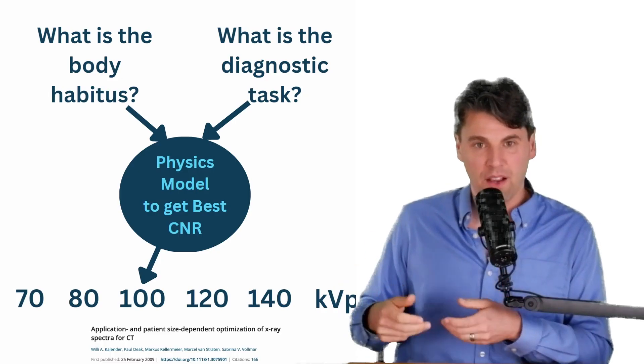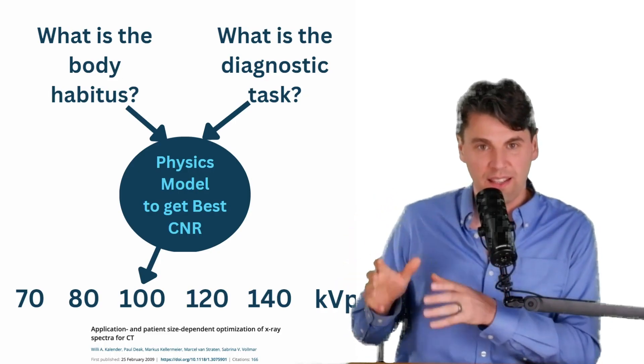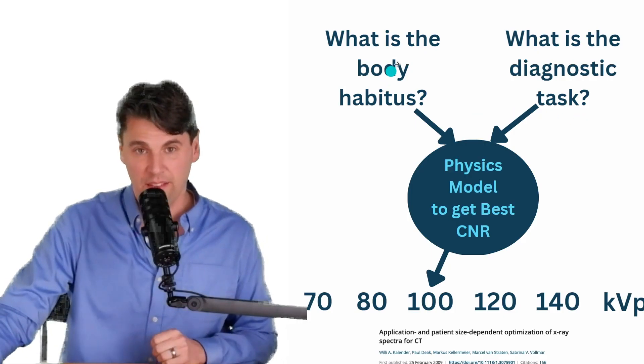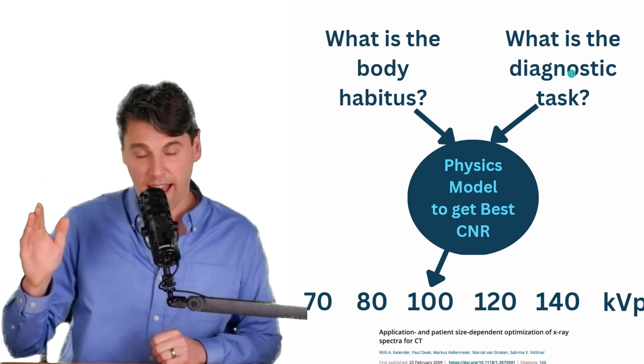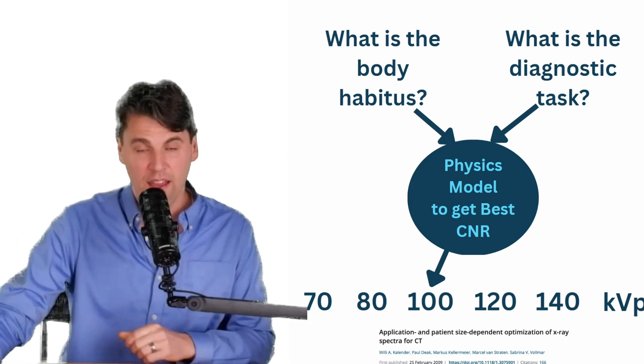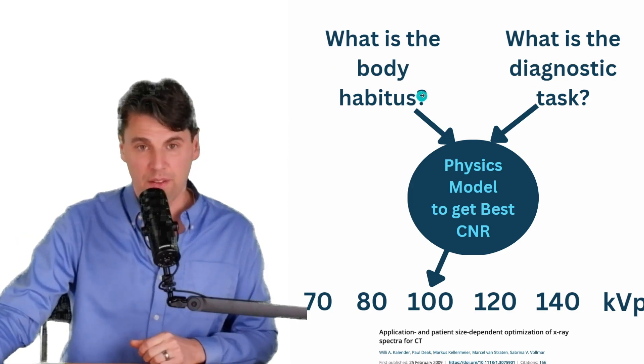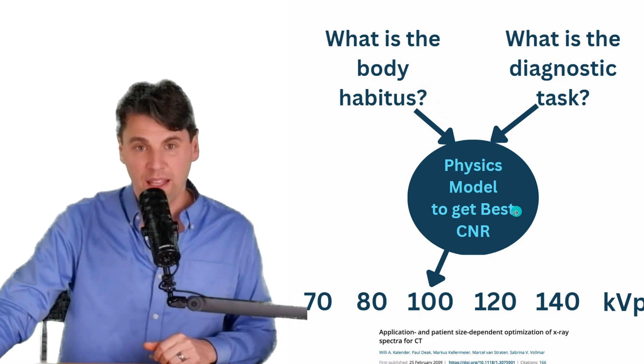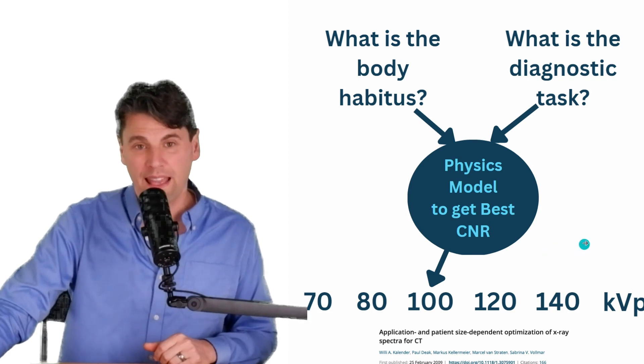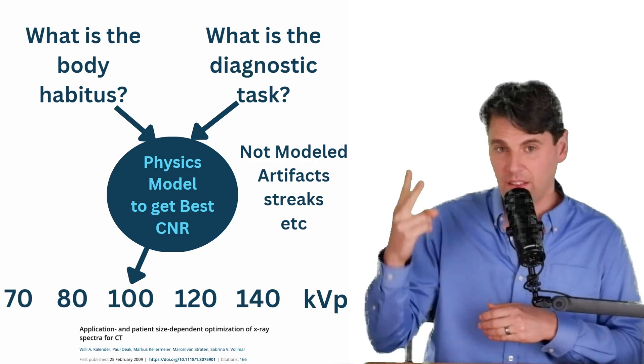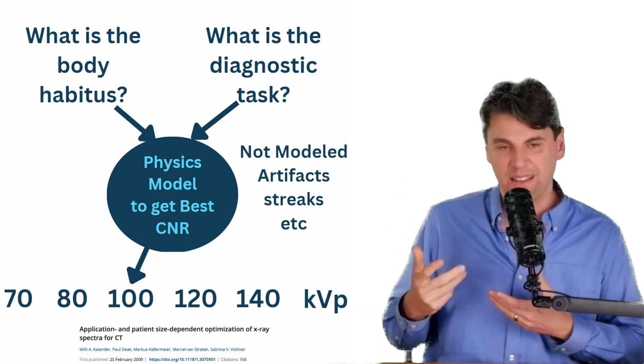So the basic physics model can help us to calculate what KVP we should use. We want to optimize here is the dose efficiency to get a contrast noise ratio. The contrast noise ratio is going to depend on these things here. What's the diagnostic task? So the two different materials that we're going to be looking at in that contrast task, and what is the body habitus? So how big is the object that we're trying to get through? And from those things, we can actually just use a physics model in order to compute what the KVP we should use on the system. Note that some of the other subtle things like the artifacts and the streaks, those aren't explicitly modeled here.